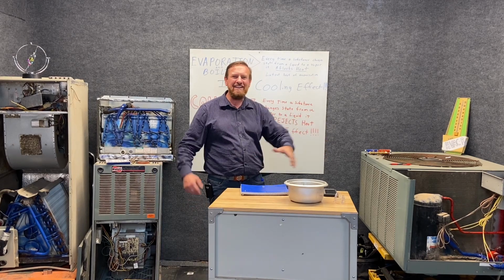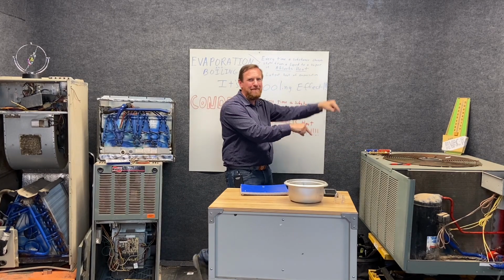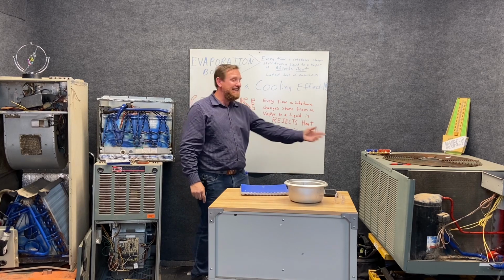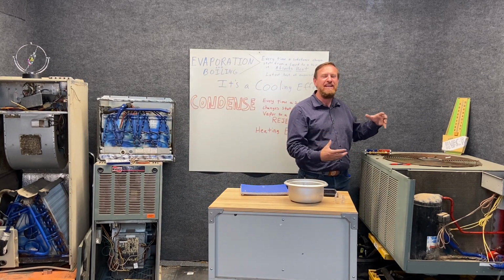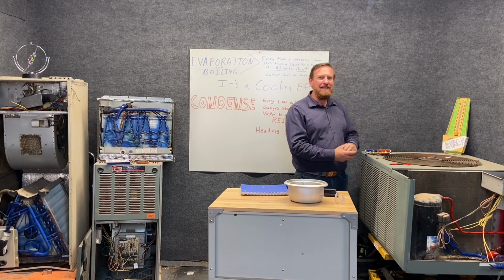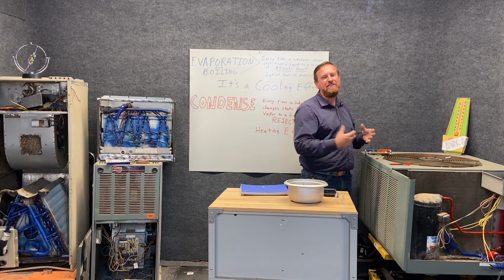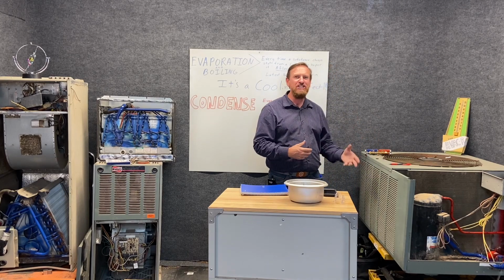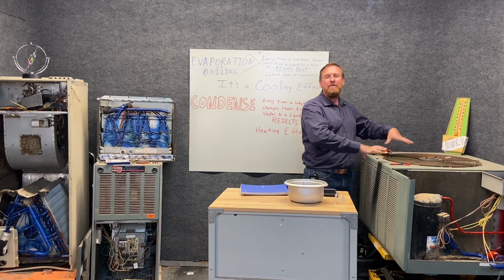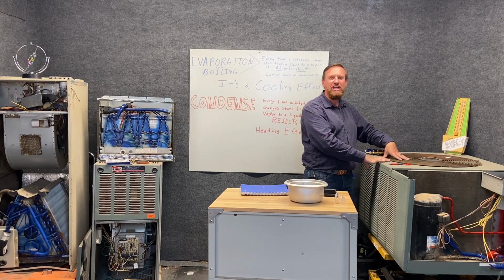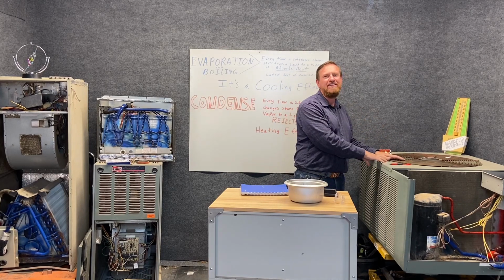Can you think of anywhere in our HVAC system that might be happening? Yes, in the condensing unit. It is a heating effect. So what's happening here is the refrigerant is changing state from a vapor to a liquid, and as it does, it rejects massive amounts of heat energy. That's latent heat. That's why I call it the condensing coil, because the refrigerant's literally condensing, changing state. It's rejecting all that hidden heat that it collected.